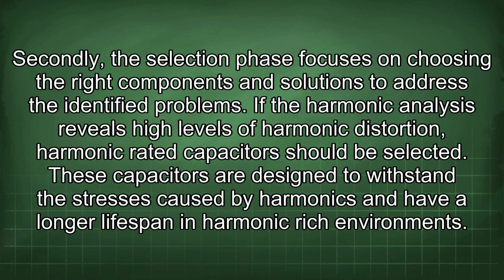Secondly, the selection phase focuses on choosing the right components and solutions to address the identified problems. If the harmonic analysis reveals high levels of harmonic distortion, harmonic-rated capacitors should be selected. These capacitors are designed to withstand the stresses caused by harmonics and have a longer lifespan in harmonic-rich environments.